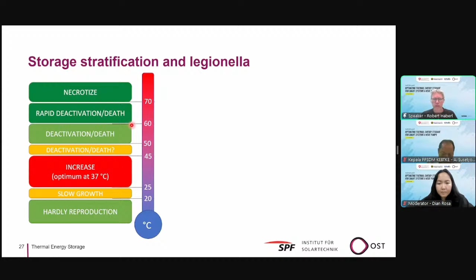degrees Celsius. Now, if you have a storage tank with a temperature distribution like that, with a very good pronounced stratification, meaning the lower part sets the height of the thermal storage tank, sets the temperature. If the lower part is cold, and you have a very rapid rise in temperature over a small region and a hot part in the end, you have a growth area for Legionella that is very small and that moves with charging and discharging of the storage tank, reducing the time where the regions of the storage tank are in a critical phase. If you have a not as good stratification, the growth area is big, and the growing of Legionella is in a bigger part of your storage tank.